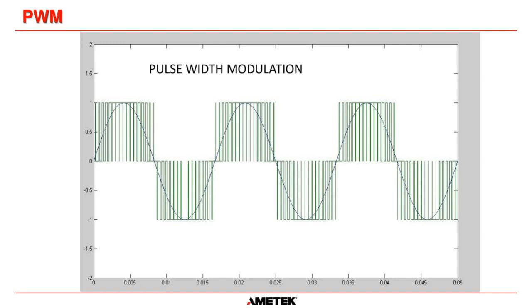So instead of switching the bridge on at 60 hertz, with these on for 8 milliseconds and then these two on for 8 milliseconds, what we're now doing is our carrier signal is 8 kilohertz. So we are switching these IGBTs on and off at 8,000 times a second, and within those 8,000 times a second we are adjusting the pulse width. If you do the math, that works out as about 66 pulses per half wave. So instead of a square wave, we have 66 pulses per portion of each square wave, if that makes sense.